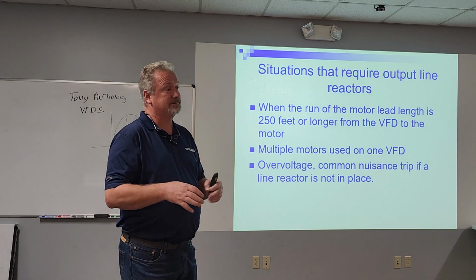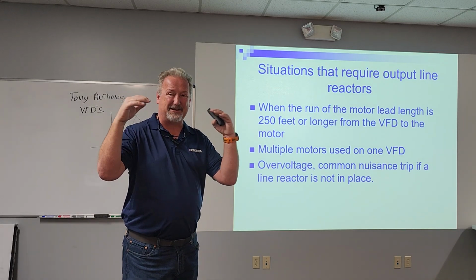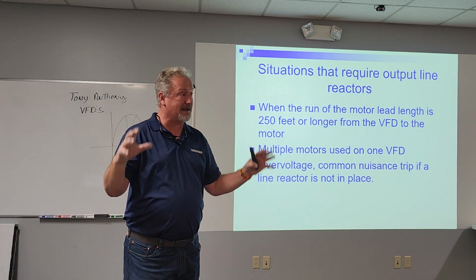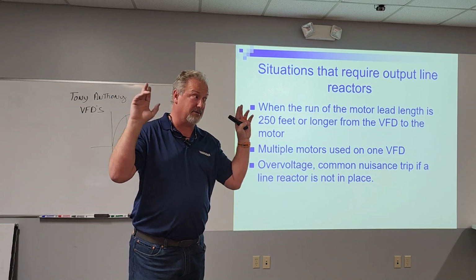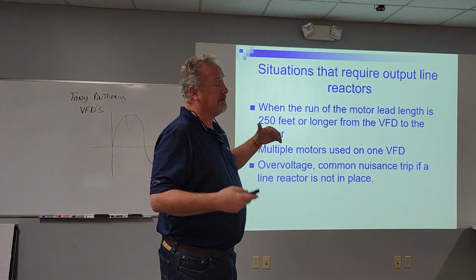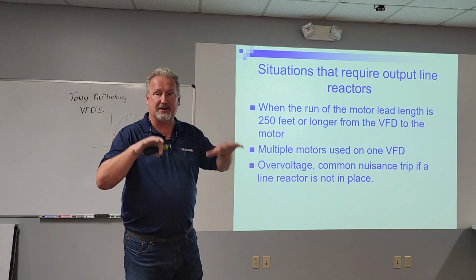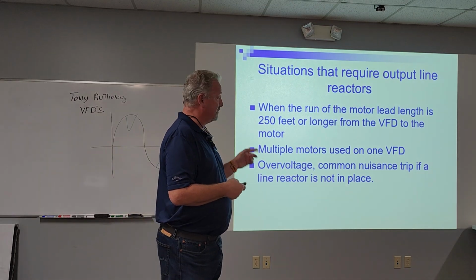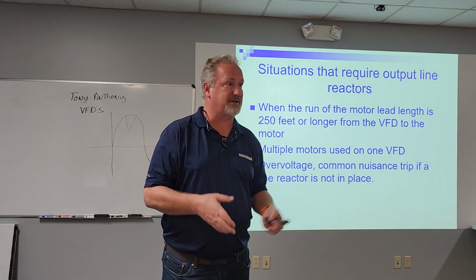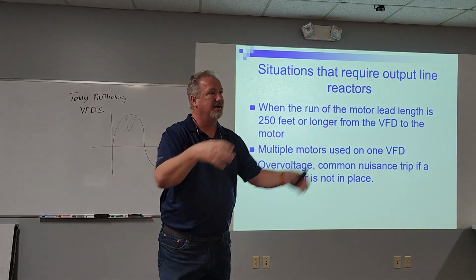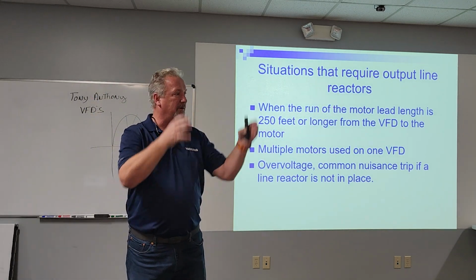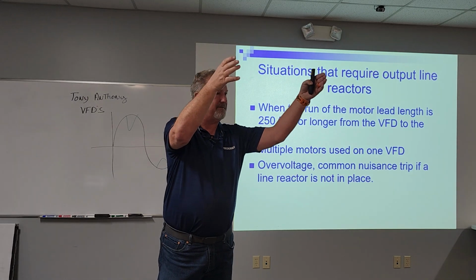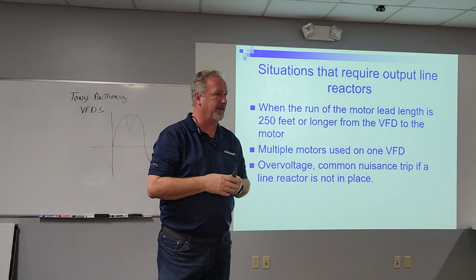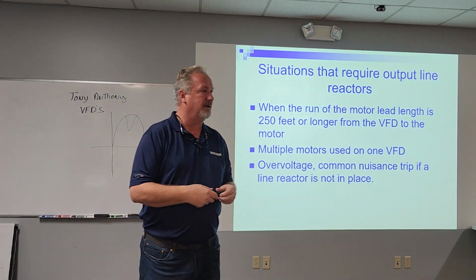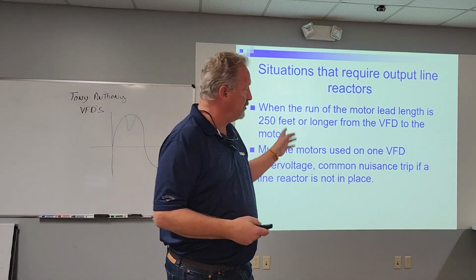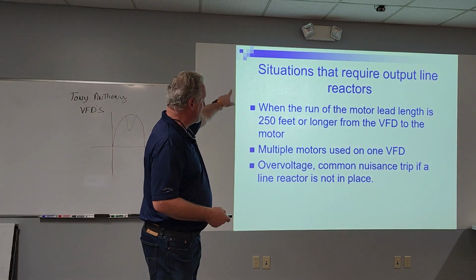But if you are doing that, there are still slight differences. Even though the motors are all running the same speed, all running together, and they're all the same motor, we recommend you put a load reactor on there just to eliminate any issues for multiple motors. Like I said, you'll see this on fan arrays. You'll see 4 motors on one drive, and they have modular fan arrays now, so they've got redundancy. If one drive fails, they only lose a quarter of the fan array, depending on how they've got it set up. The big thing is, if you do run multiple motors off one drive, you've got to think about a load reactor.